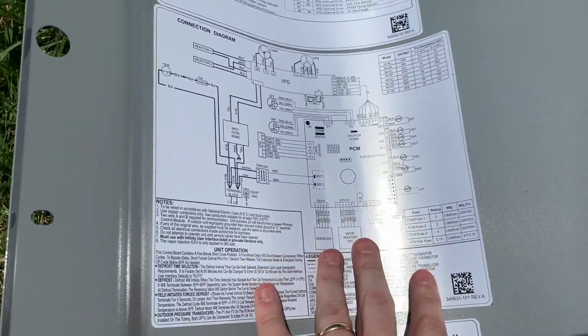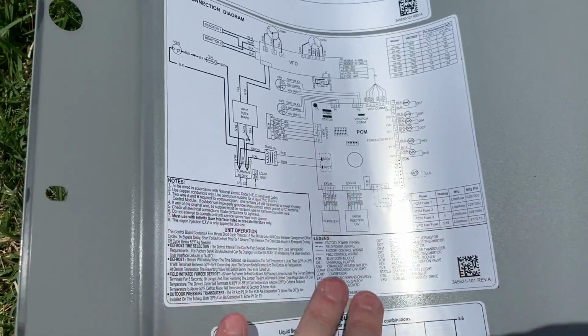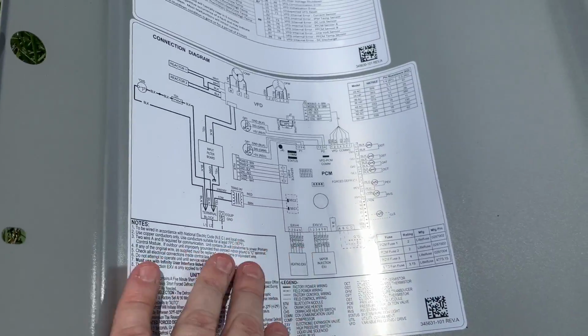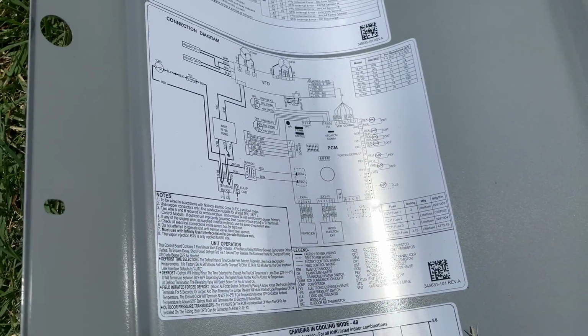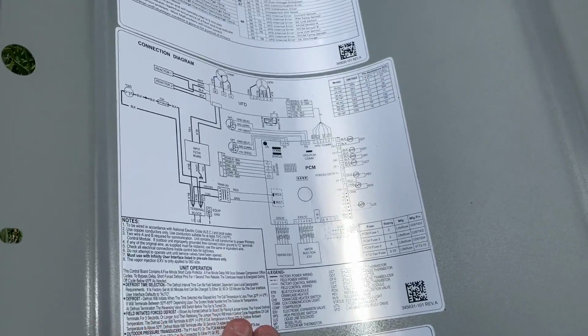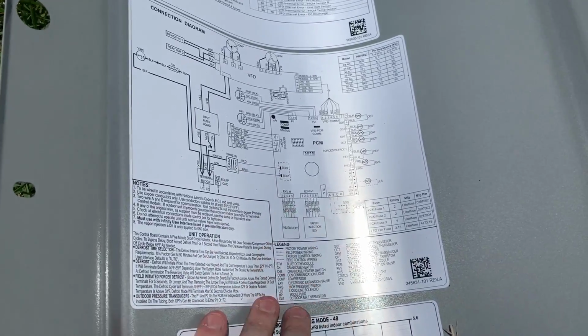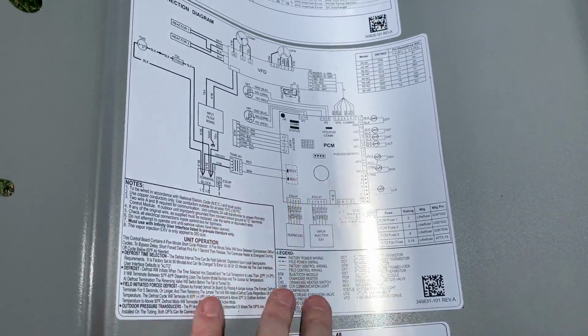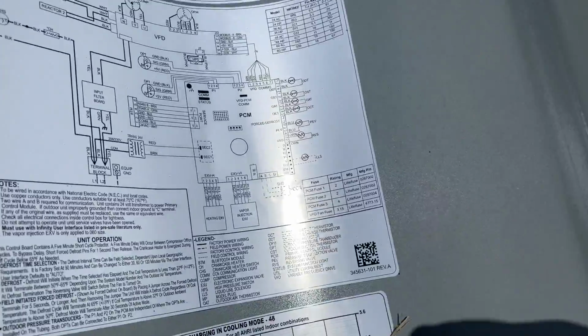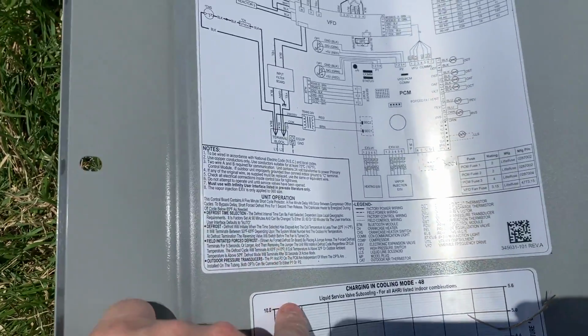Another thing is, whenever you're installing a new system, you know, just become familiarized with the components in the system and double check all the factory electrical connections. We've seen cases where there's been lugs that haven't been fully tightened and you just don't want to have those issues. So always double check. Not to say the factory's doing anything wrong, but you just always want to double check everything.